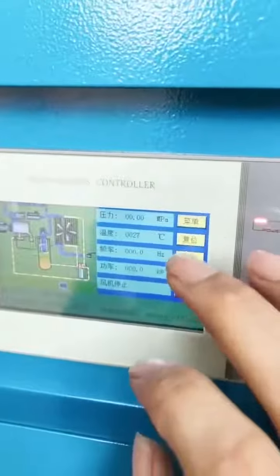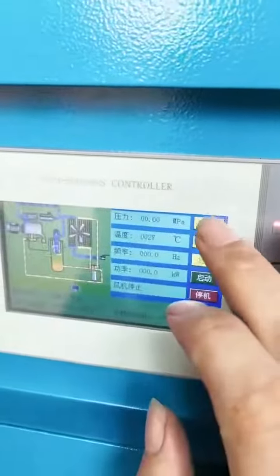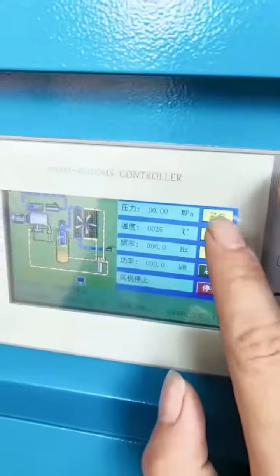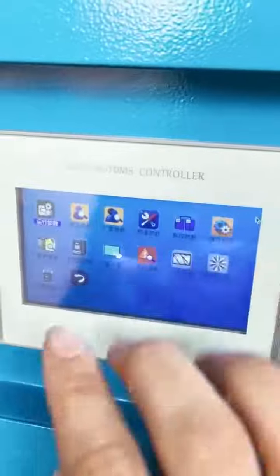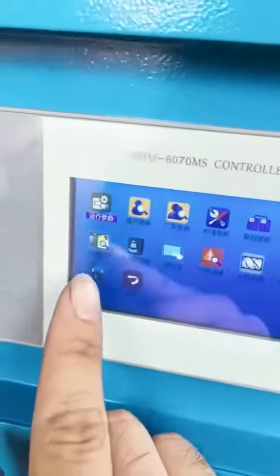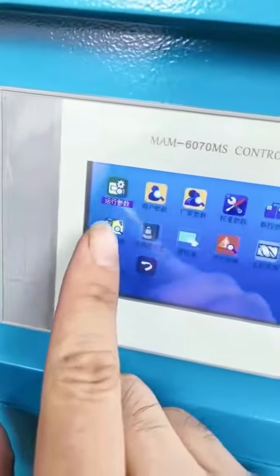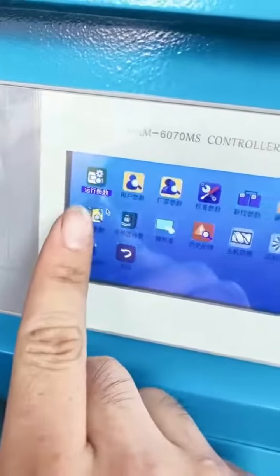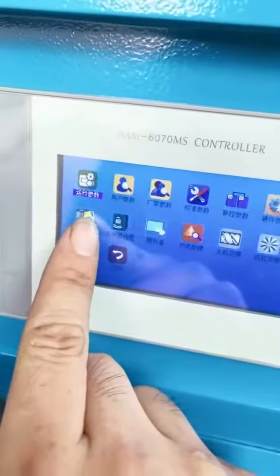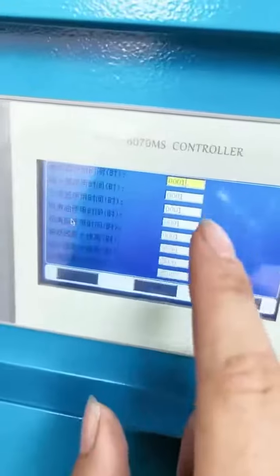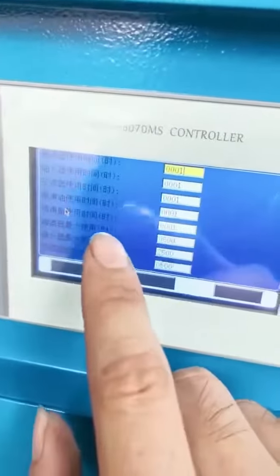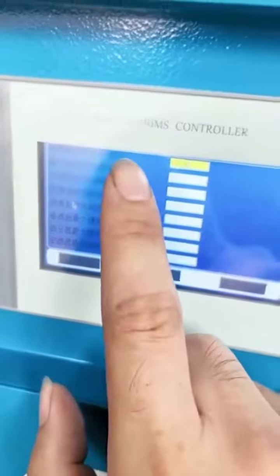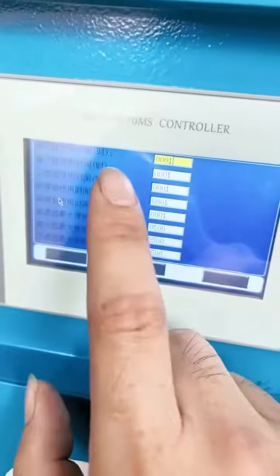To adjust your compressor maintenance time, first click Menu. Second, click Consumables Parameters on the second line, and then adjust the maximum time according to your own requirements.